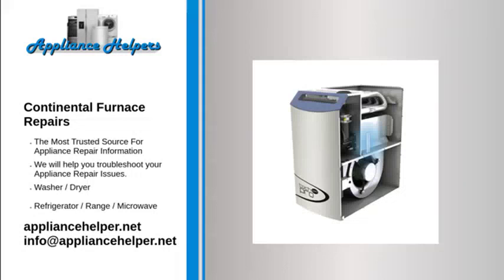At the end of the cycle, the fan should run for about 2–3 minutes after the burner shuts off. If the fan does not shut off after the time delay, then the fan limit control on older units may be sticking and require replacement. During this time you can check the temperature rise across the furnace.